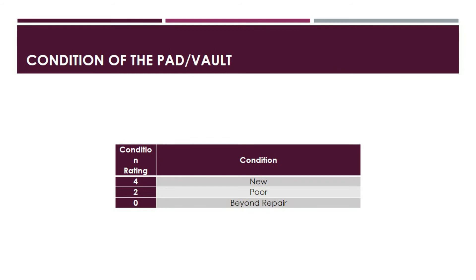The last category applies only to pad mount or vault transformers. These ratings specifically regard the condition of the pad if it is a pad mount transformer, or the condition of the vault if it is a submersible vault transformer. Again, this category has only three ratings: 4, 2, and 0. A rating of 4 means the pad or vault is in good condition, or what we call new. A rating of 2 means the pad or vault is in poor condition and remedial action is required. A rating of 0 means the pad or vault has been degraded beyond repair.